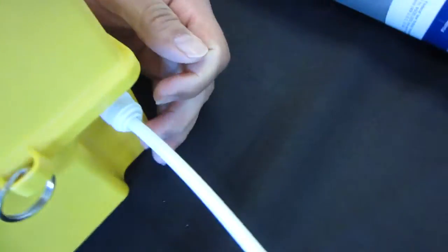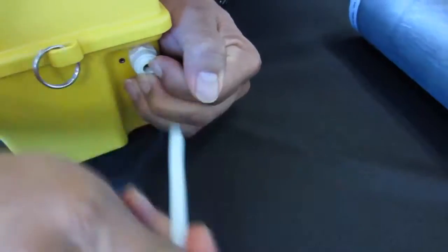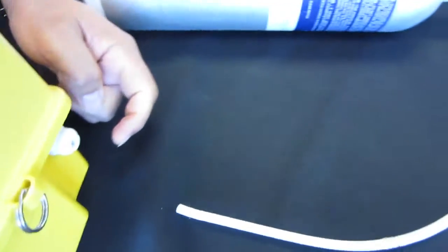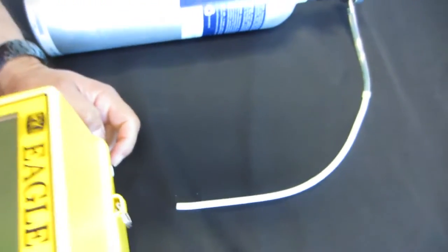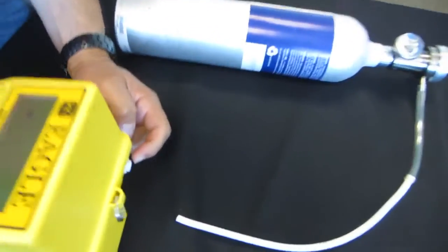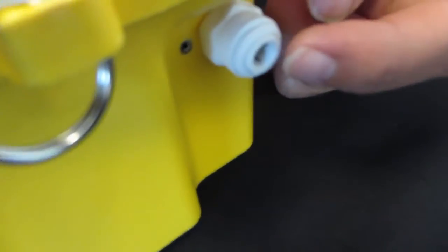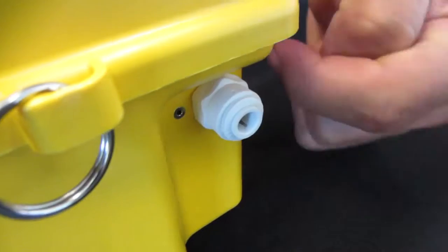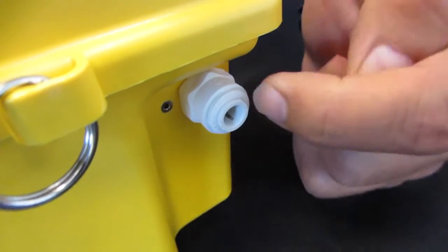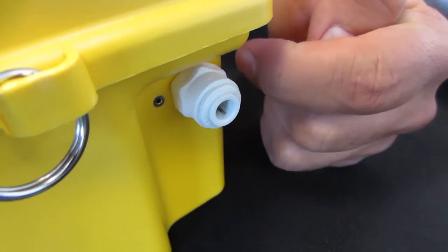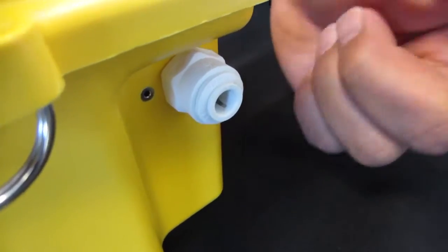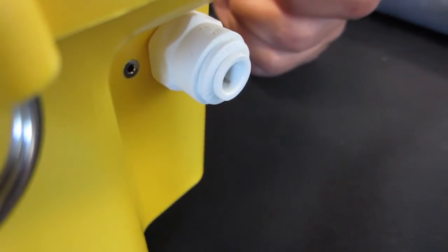Better grip on it. Okay, there we go. If you don't push this little collar in toward the unit, you cannot pull the tubing out. So it's important to push this collar in, then pull the tubing out, because otherwise the tubing will remain locked in place. That's an important point.